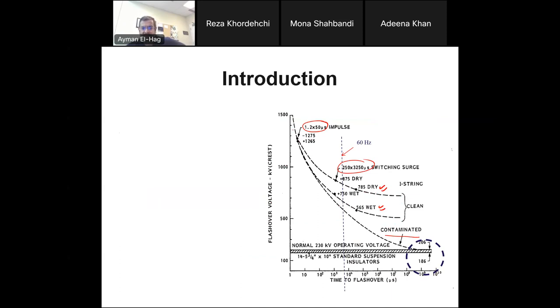So we have here basically three curves. This is for I string. When you say I string, it means that the insulators are in vertical position, like a little I. There is V string as well, which is when you have two insulators in this configuration, basically we use it whenever there's wind, for mechanical support of the insulation systems. So this is for an I string, okay? Now here is basically the 1.2 by 50 microsecond. These three curves for dry, wet, and contaminated are not really different from each other.